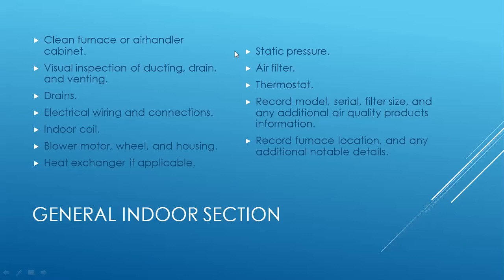I would do a static pressure reading. Get in the habit of doing that more and more, because with all these new ECM and X13 motors, they're very static pressure dependent. If you cause them to run under extreme static pressure, they want to operate at 1.0 and under.